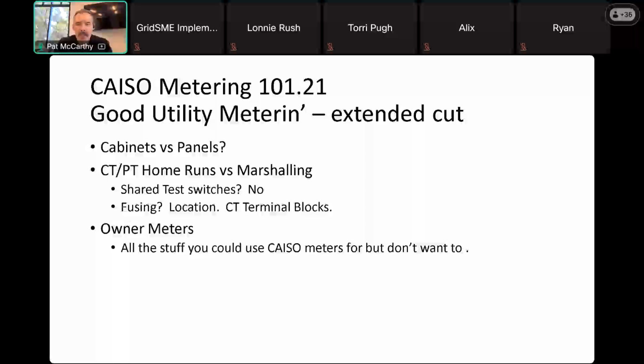I put fusing on there with a question mark. Fusing from a revenue metering perspective is a good way to protect your meters. It's also a good way to lose a little bit of money. I've found partially blown fuses a couple of times, meaning there was a little surge that didn't pop the fuse, but the fuse became slightly resistive. You're dropping a couple volts—maybe 3 volts, which is 2.5% of your voltage on that phase—and that means your watt hours are 2.5% less on that phase. You're losing power. There are ways to look for that.